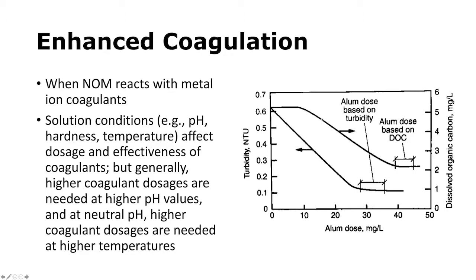Enhanced coagulation describes the situation where natural organic matter removal is the primary objective. Coagulation-flocculation can achieve reductions in both turbidity and natural organic matter concentration, and these two objectives may require different coagulant doses. For example, the alum dose based on turbidity might be around 30 mg/L, but achieving dissolved organic carbon reduction might require a higher dose of around 40 mg/L. Solution conditions such as pH, hardness, and temperature all affect dosage and effectiveness. Generally, higher coagulant dosages are needed at higher pH values and higher temperatures.